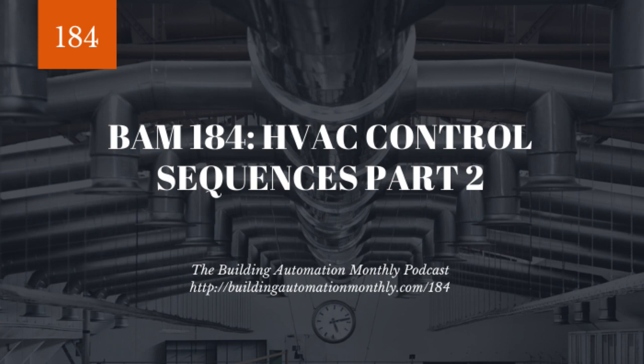They start to heat up, and that creates heat. And so that is how we introduce heat as well. So you've got DX cooling, and you've got gas or electric heat on rooftop units. Additionally, we have a supply fan. Occasionally, we will have an outside air damper and return air damper. Sometimes we will only have an outside air damper. If we do have an outside air and return air damper, they are normally interlocked and opposed. So meaning that if the outdoor air damper is 100% open, the return air damper is zero. If the return air damper is 100, the outdoor air damper is zero. So we kind of see how that works right there.